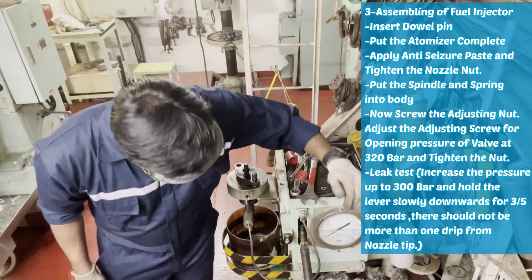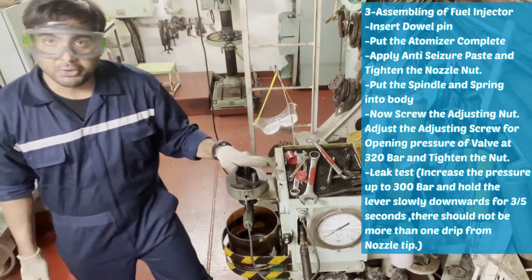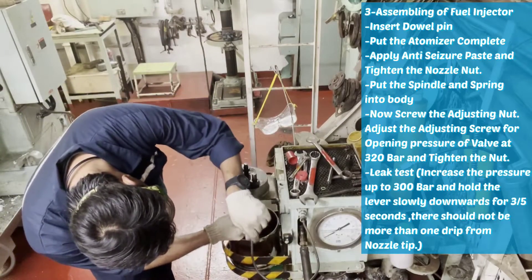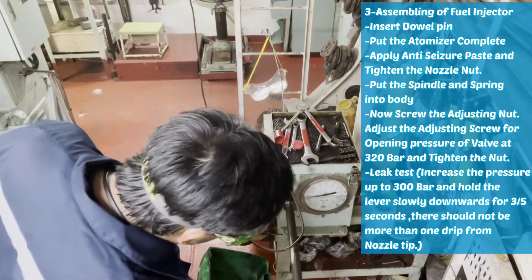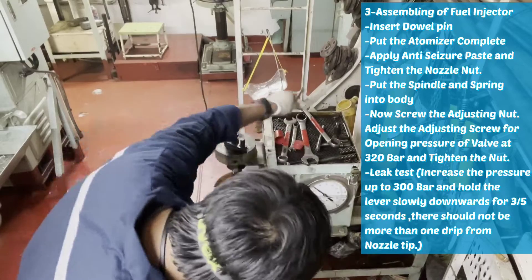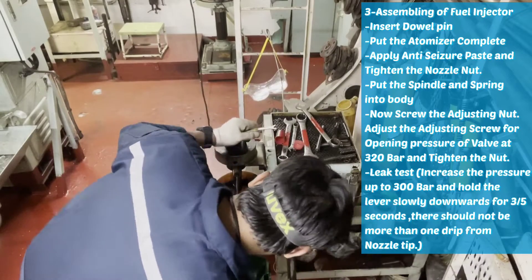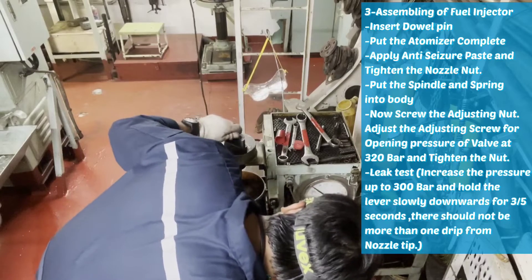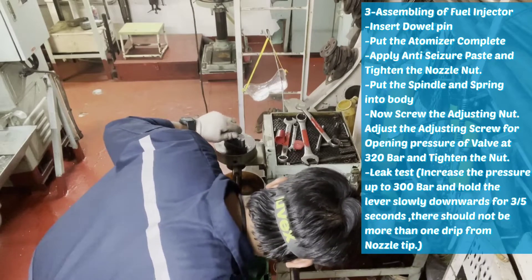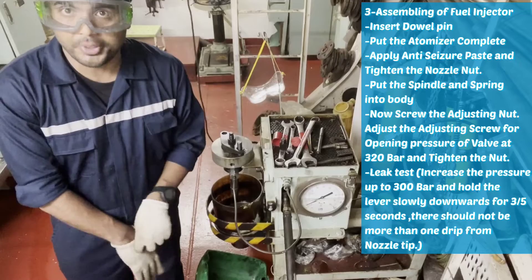Now we have to adjust the pressure to 320 bar, because the opening pressure is 320 bar for this injector. Now we will adjust this one. Slowly, slowly we will raise the pressure with the help of this handle. So the pressure is adjusted to 320 bar for opening the valve.